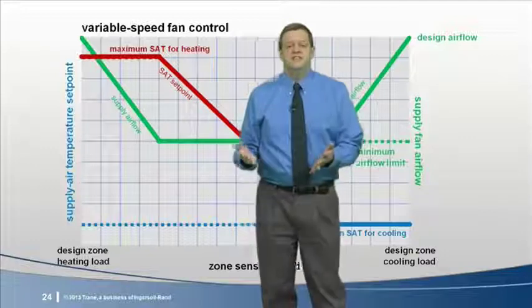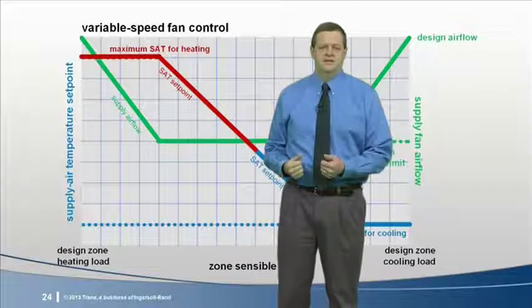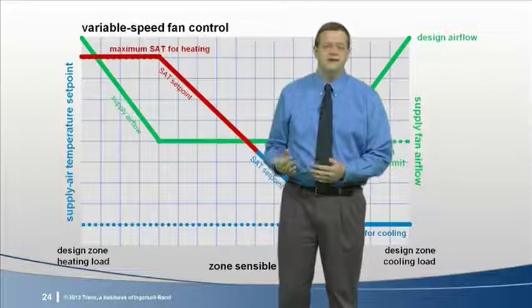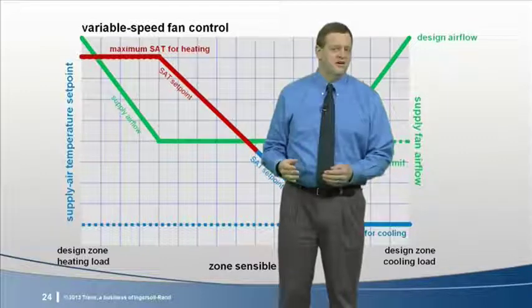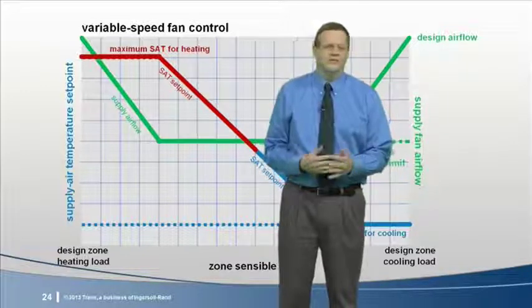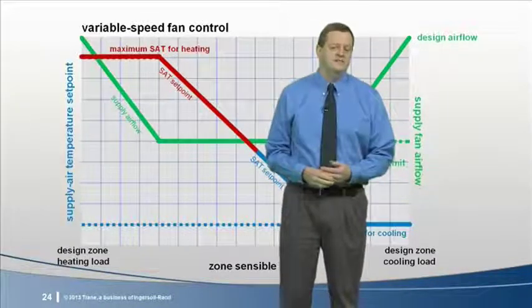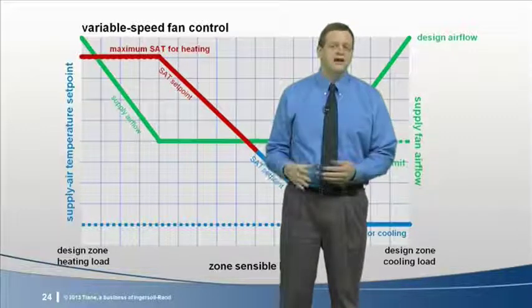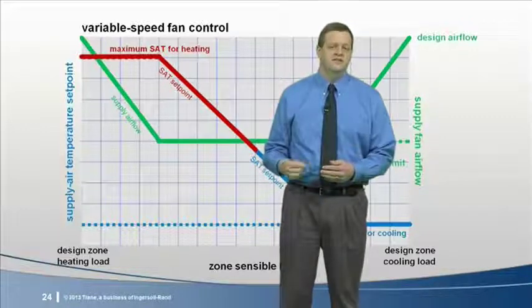Now, this is just an example to demonstrate the concept. This control can vary by manufacturer. Plus, there are nuances that depend on whether chilled water or DX is used for cooling, and whether or not the type of heater used can support variable airflow.